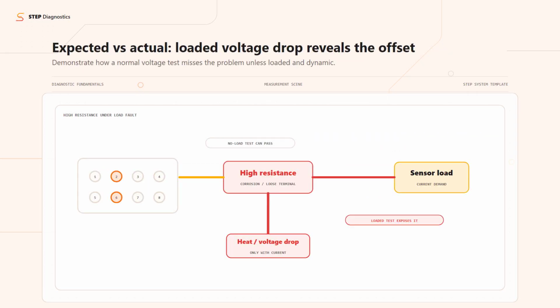A continuity or unloaded voltage test often passes, missing the actual issue because no current flows. Only a loaded ground voltage drop test, performed during the real symptom or induced by manipulating wiring, will reveal the true offset. Comparing the loaded voltage to expectations is critical before condemning any components.